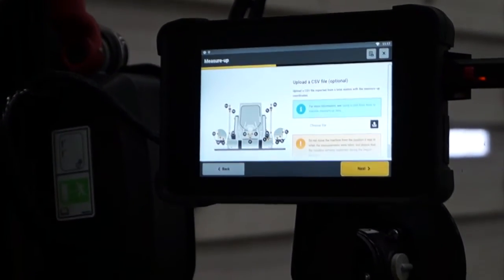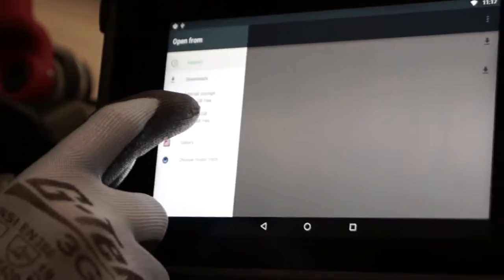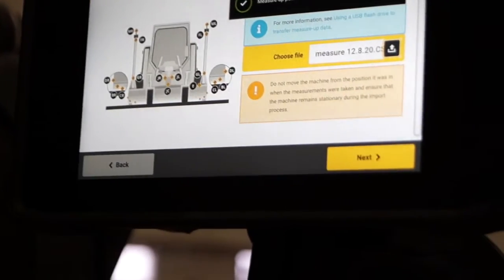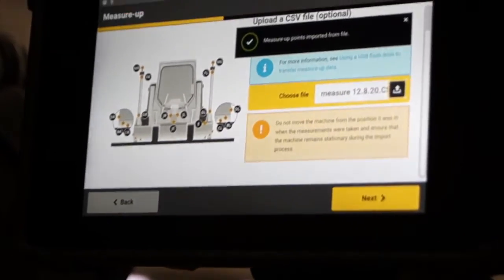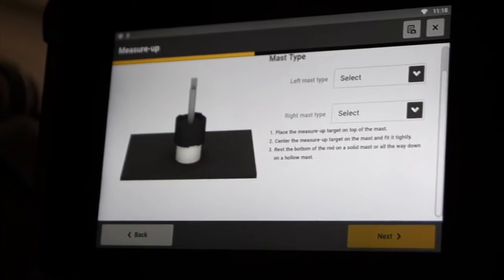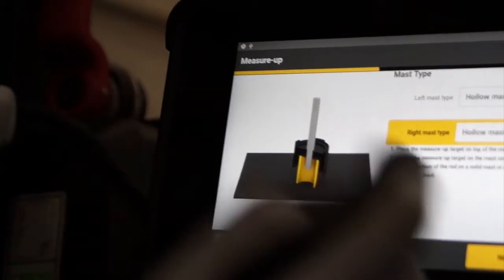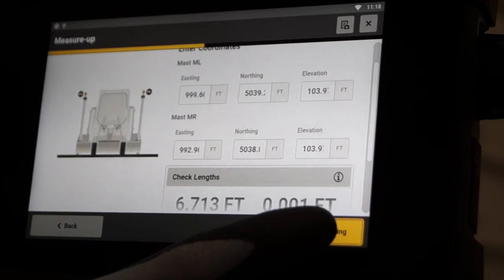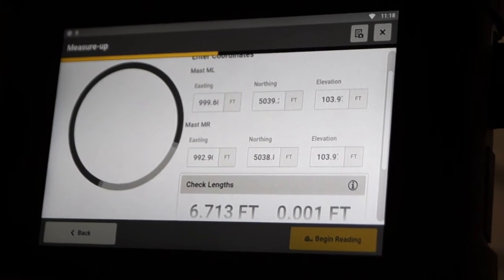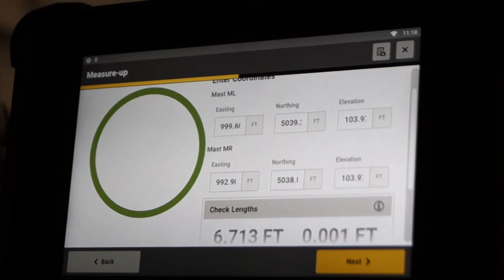The measure up has a specific screen where it can take a CSV file. We've uploaded the file from the USB drive into the machine. This automatically enters all of the values throughout the measure up, as you can see. First, we'll select our mast. The mast is fixed, yet it is hollow like the picture shows. We then move on. You can see here our points. It takes a calibration.